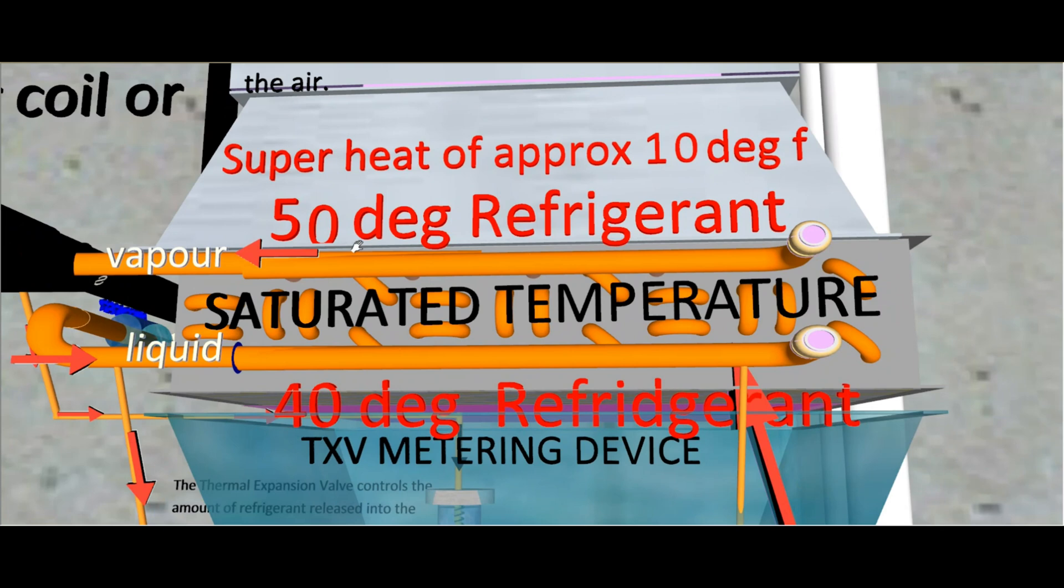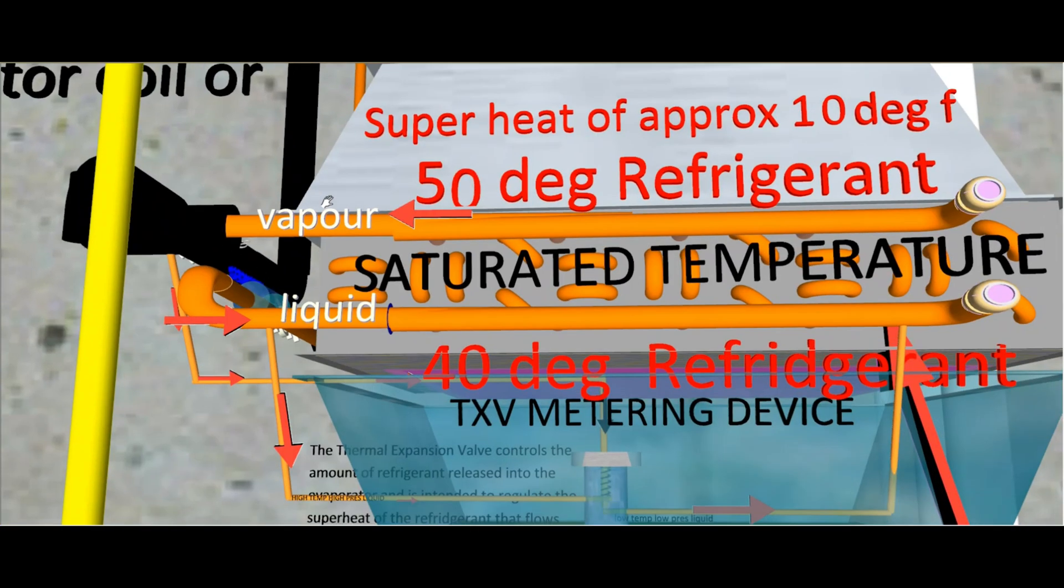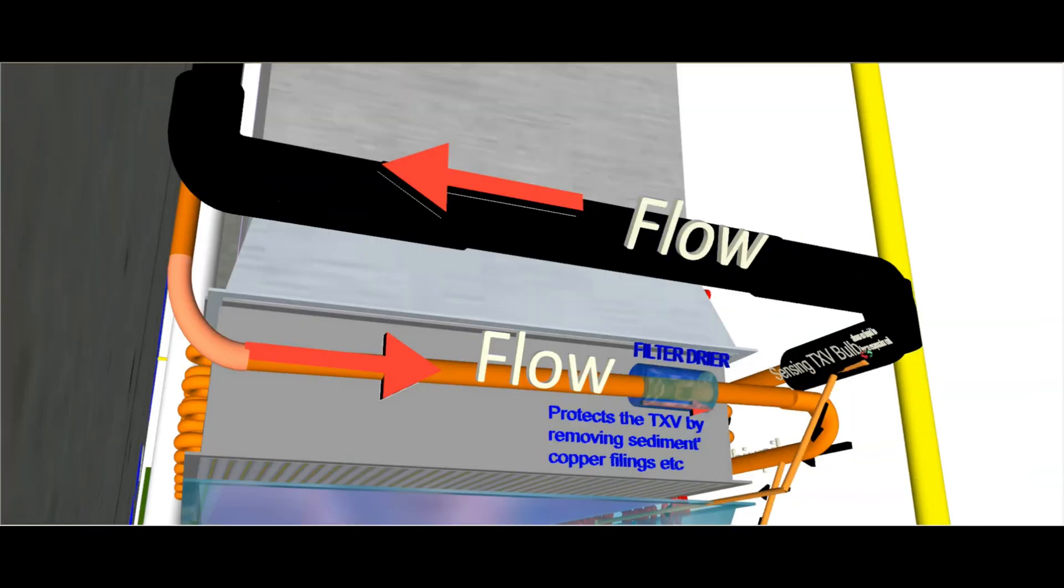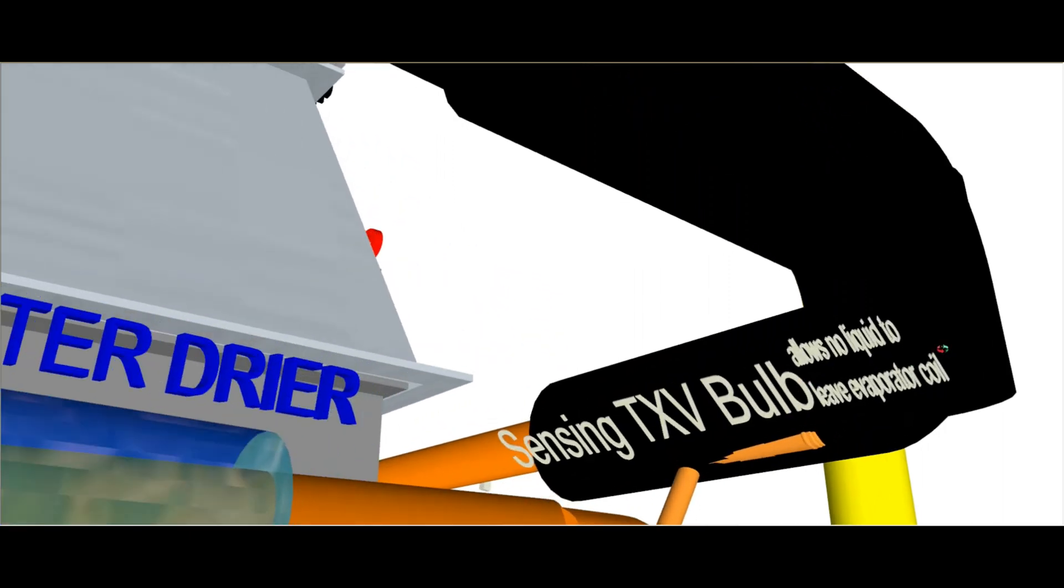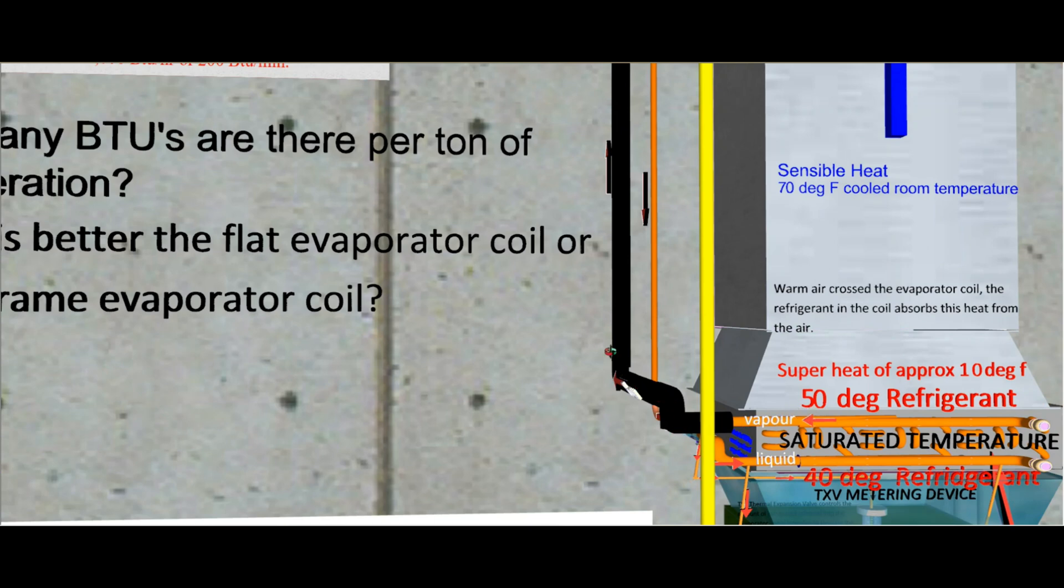So that's what we call superheat when it comes out of the coil. Now we have to make sure—or this valve that regulates it has to make sure—that there's only vapor coming out of this coil, right? Because when it comes out of the coil, it's going to go back to the compressor, and we can only handle vapor in the compressor. So this TXV valve actually has a sensing TXV bulb that is strapped adjacent to the suction line, and it allows no liquid to leave the evaporator coil. That's its job. We can't have any liquid come out of this evaporator coil. So now it's strictly vapor that's going to come. Now it's 50 degrees here, right, coming out.